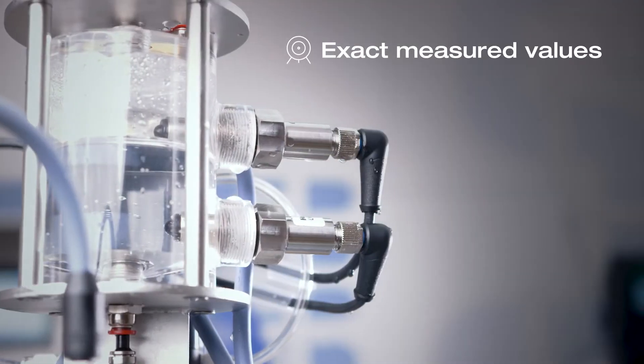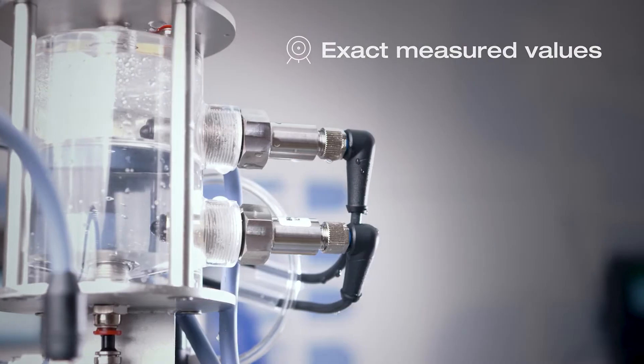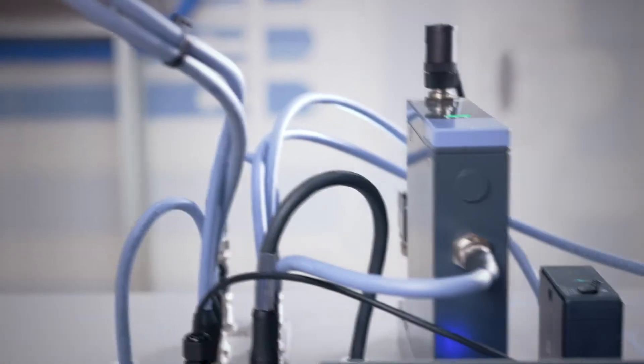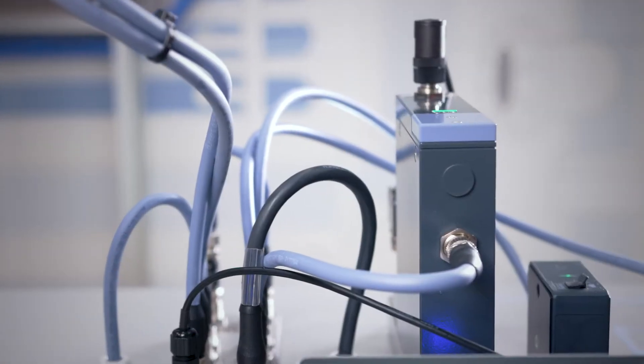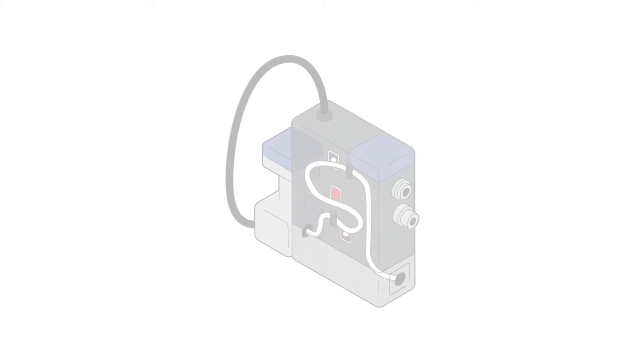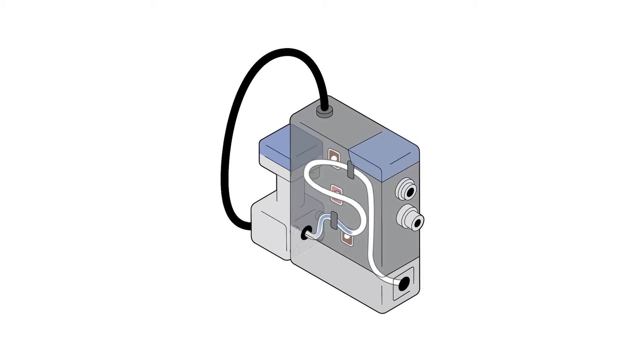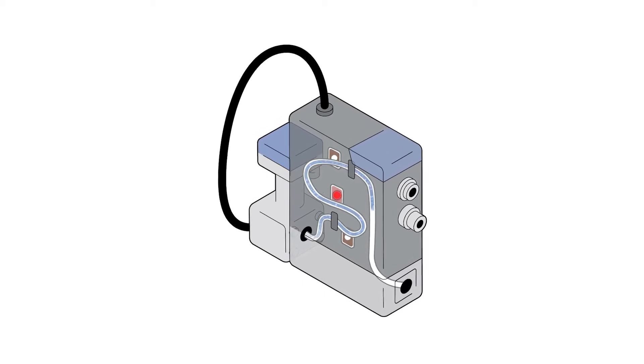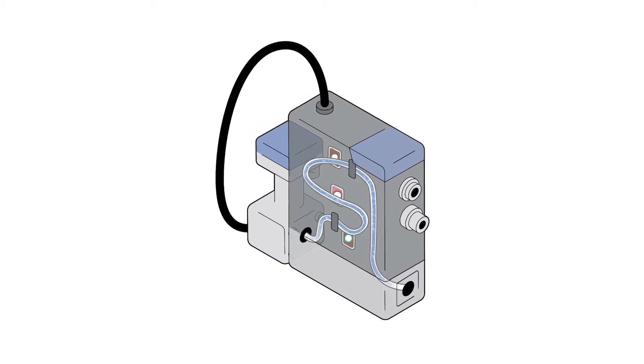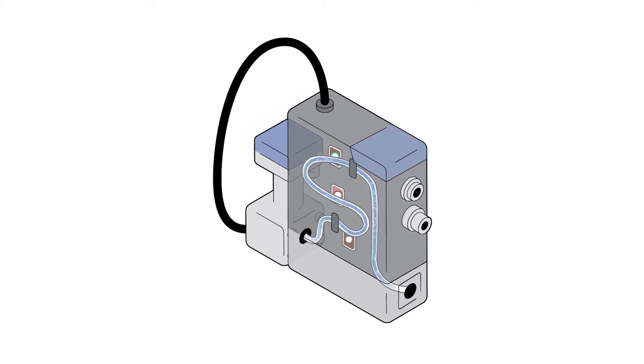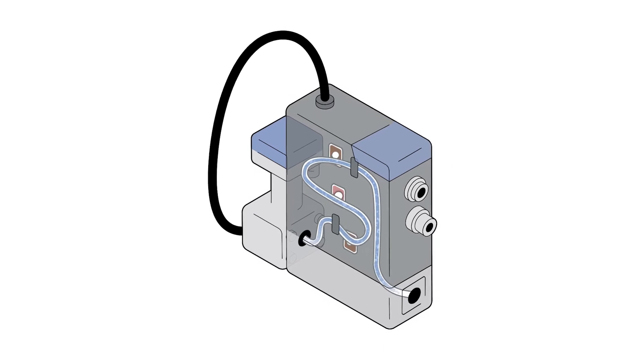Unlike conventional measuring methods, the measurement is based on the Coriolis principle. The pure mass measurement is thus not dependent on the medium, temperature, and pressure, which is why the device, once set, can be used for nearly any kind of liquid.